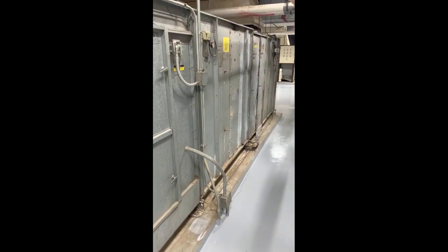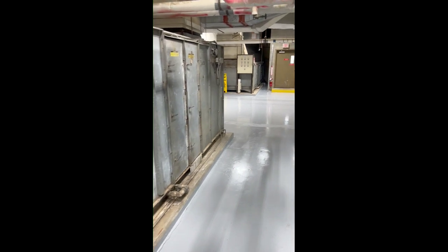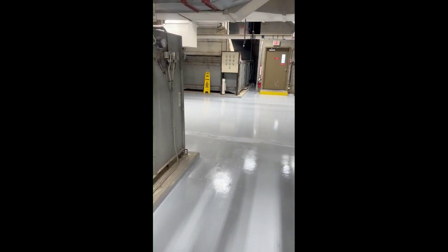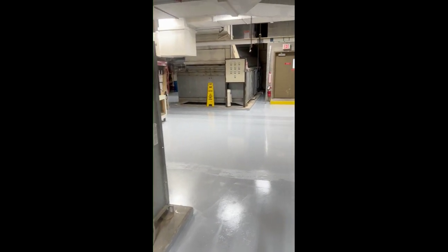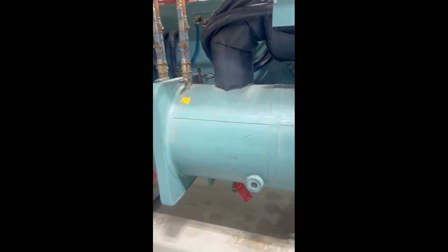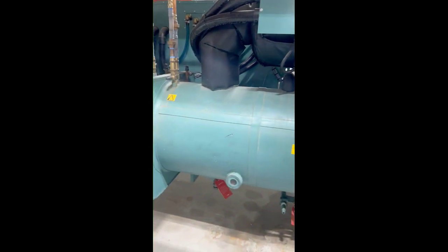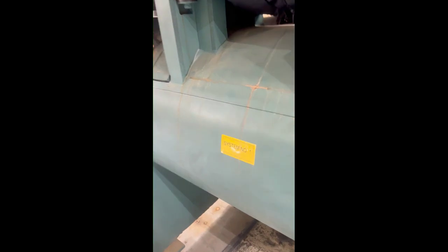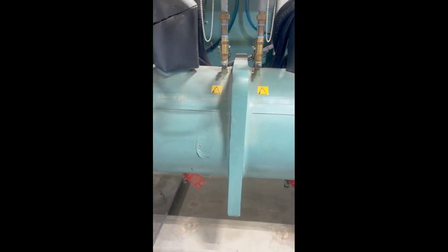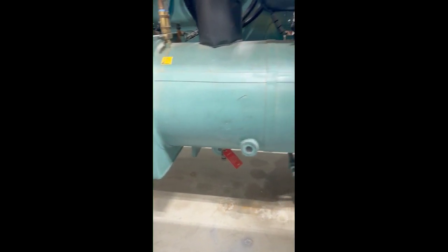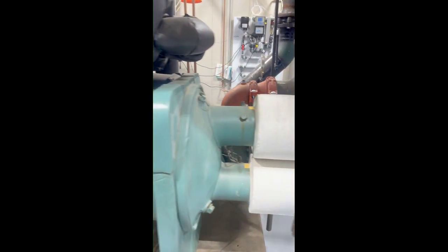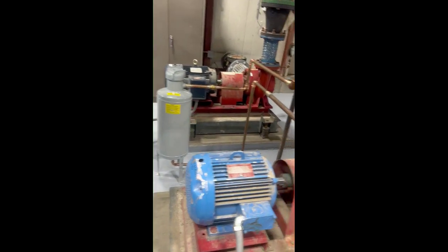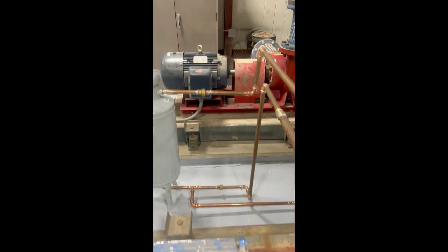So one thing I'm hearing that I'm not liking, I hear a high-pitched whistle. So the first thing I'm wondering is, what is that noise? My chillers are off. This is my main scroll chiller. It's a 2-circuit chiller. So again, here's circuit 2, circuit 1. The dividing point is this bulkhead that's right in the middle. So I have basically 2 chillers on 1 frame here. That system is off. It's not leaking right now. My cold water pumps are not in the on position.